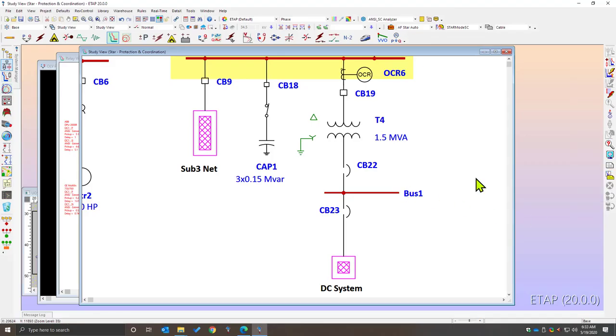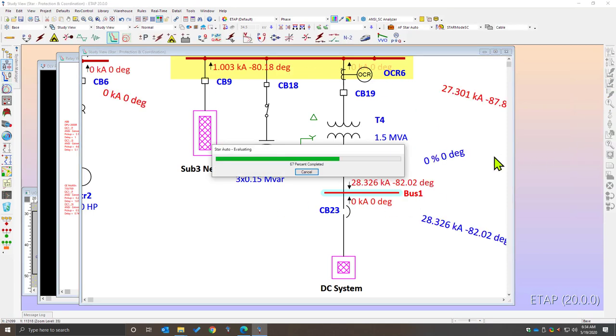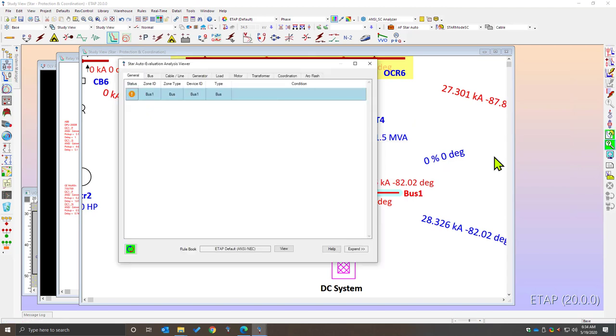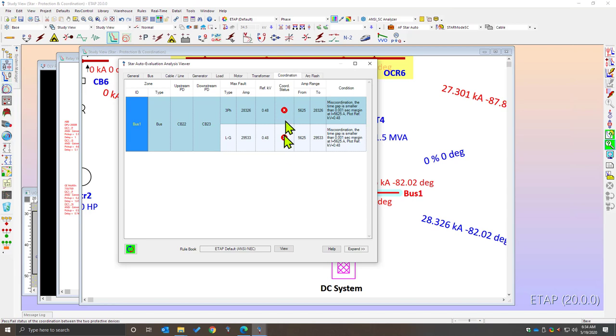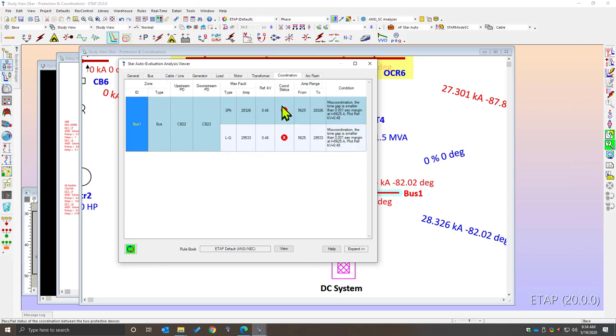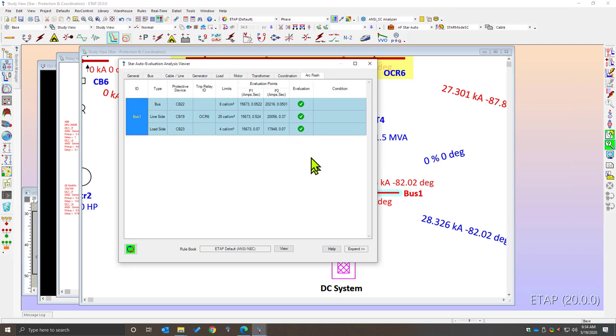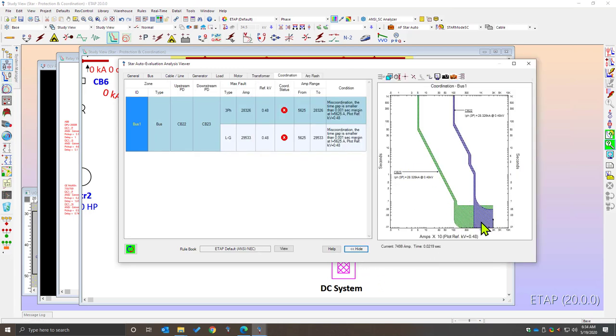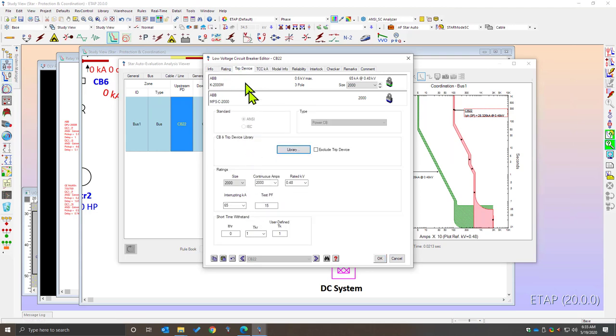Automated Arc Flash evaluation is built on top of the existing STAR automated evaluation program. You can simply select a single piece of equipment or multiple sections of the diagram to perform an automated evaluation. In a few steps, the program can automatically evaluate the protection and coordination of a single zone or multiple zones in your power system network. For this example, we can see a violation in our protection coordination. However, we have passed our Arc Flash evaluation, so an optimal setting must be chosen that balances short circuit and Arc Flash based coordination.